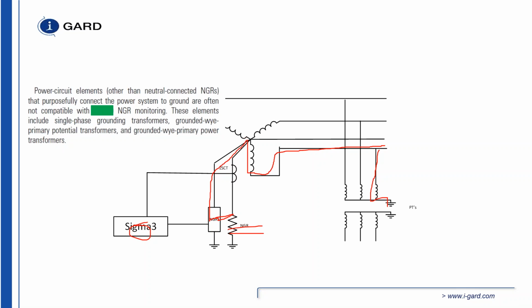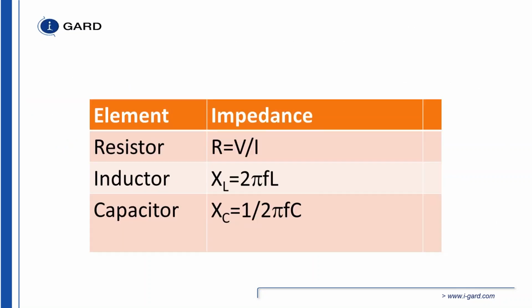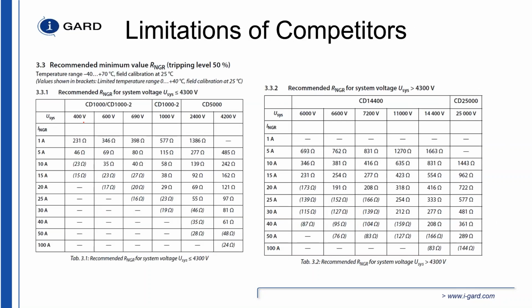Alrighty, next question. If the competitor is limited to 20 ohms, what typical NGR applications does this impact? If you look at their chart, this chart came from their manual. So they're limited to 100 amps, according to this chart. So they have 2 types of sensing resistors. They use one for less than 4,300 volts and one for greater than 4,300 volts. And you can see that their limitation is here, right? 100 amps up to 25 kV.